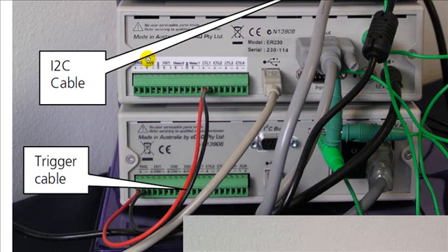This photo shows the high voltage sequencer, this top unit, and these are the digital outputs here. This unit is the C4D system, and this is the trigger. So you can see you can connect the control 1 plus using the red cable to the trigger plus of the C4D system, and from the high voltage sequencer, control 1 minus, the black cable, goes to trigger minus of the C4D data system.